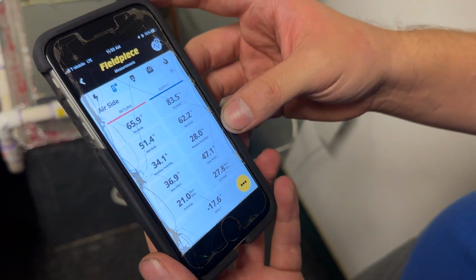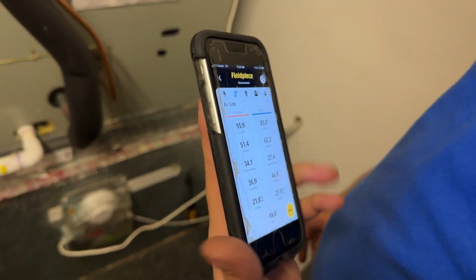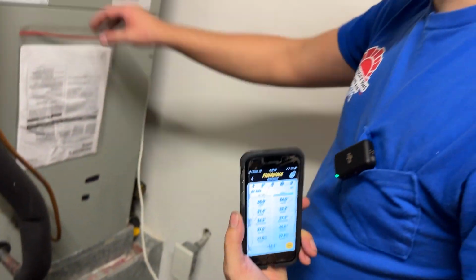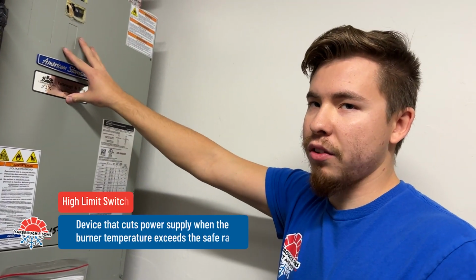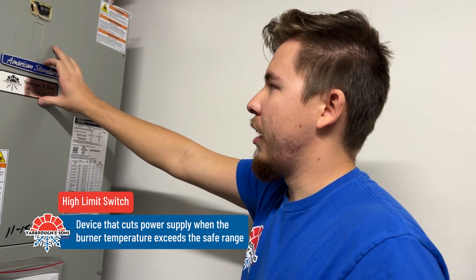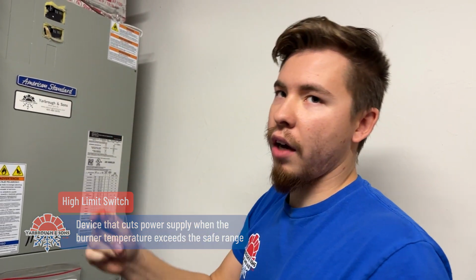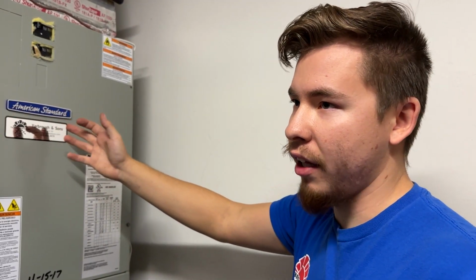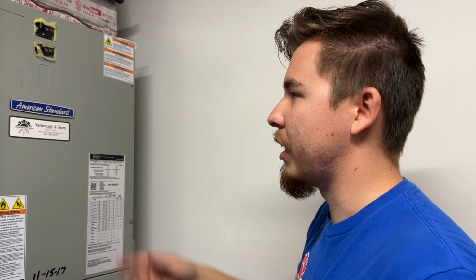So right now you want a temperature split with these air handlers. They can get up to around 140, but there's another safety switch in this one, they have high limits. So if they do get too hot and your system doesn't recognize it, the high limit will kick off the unit and let us know, hey, there's a problem. Then we start diagnosing why this high limit is going off. That's when we start diagnosing the heat strip. Maybe it's pushing off too much heat, or the breaker's going bad. Just gotta wait now, let the heat rise, let the temperature split do its thing.